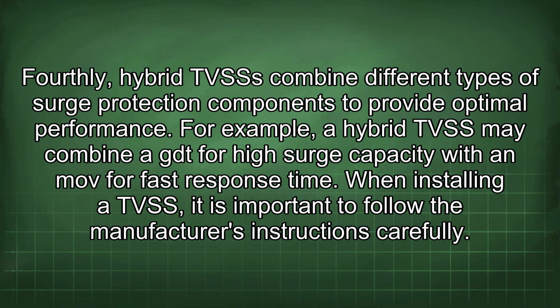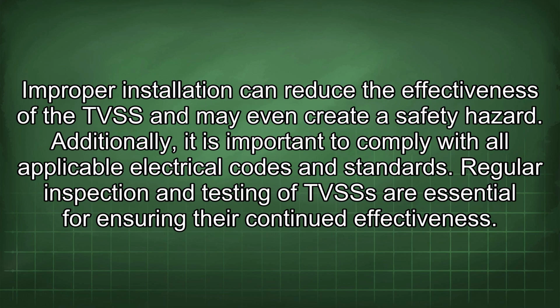Fourthly, hybrid TVSSs combine different types of surge protection components to provide optimal performance. For example, a hybrid TVSS may combine a GDT for high surge capacity with a MOV for fast response time. When installing a TVSS, it is important to follow the manufacturer's instructions carefully. Improper installation can reduce the effectiveness of the TVSS and may even create a safety hazard.